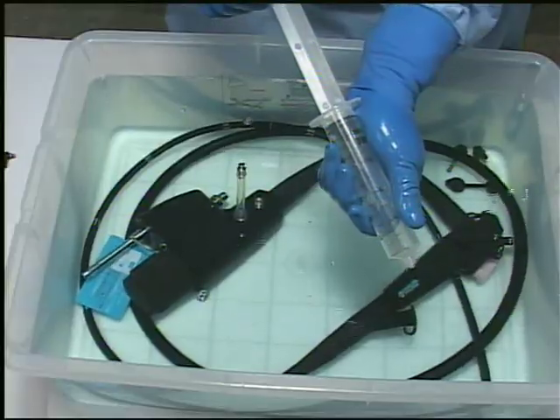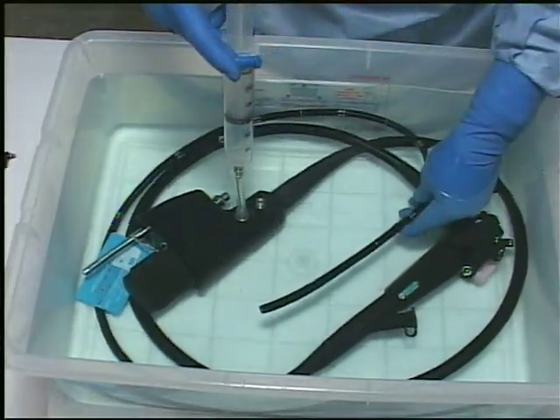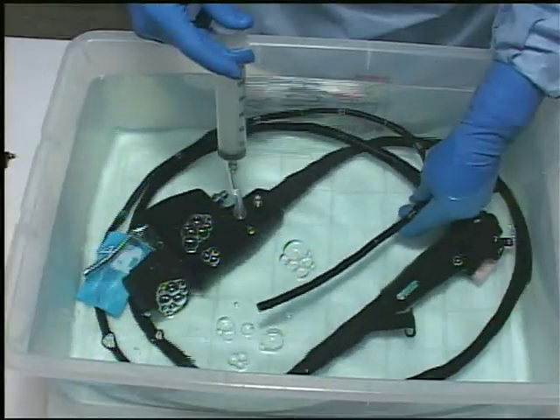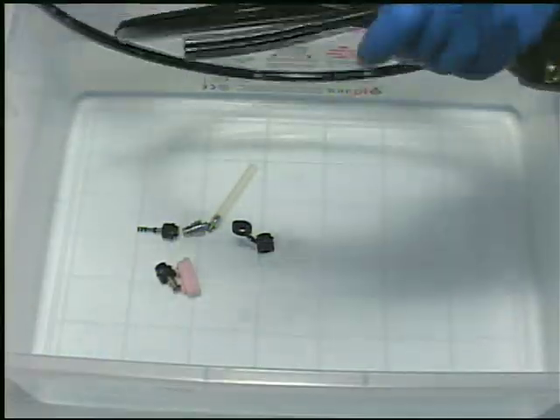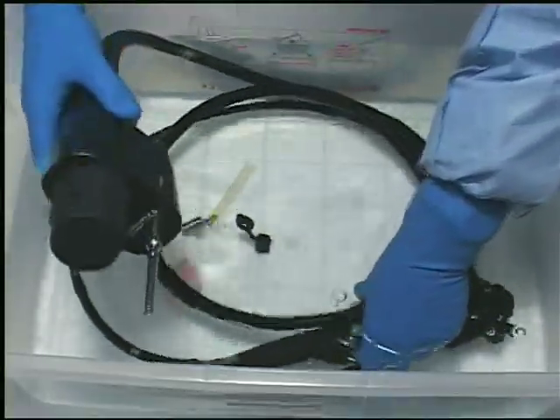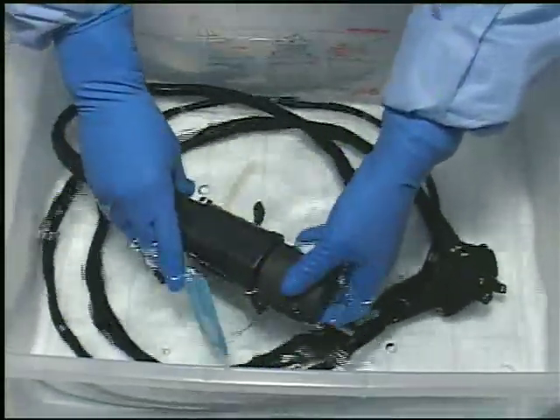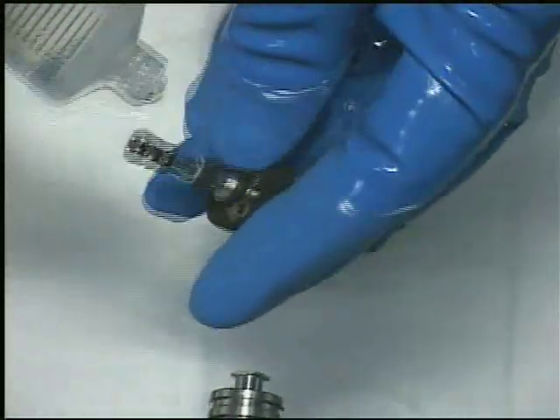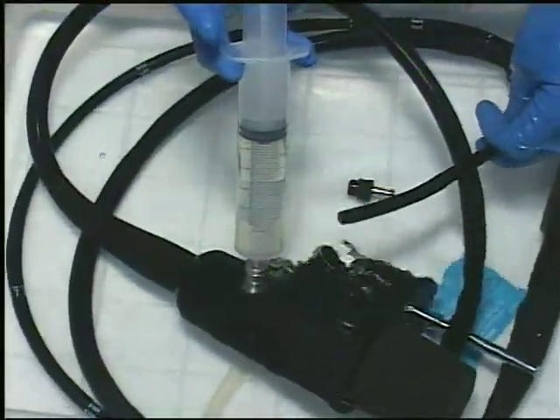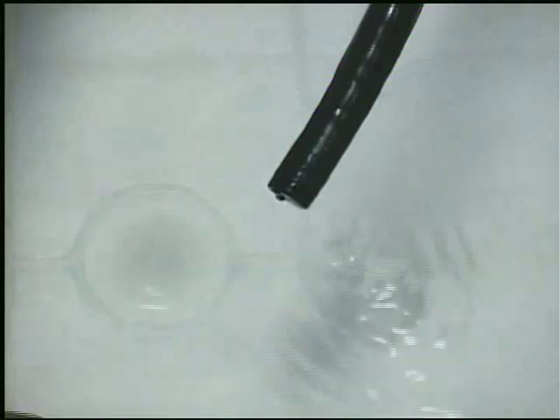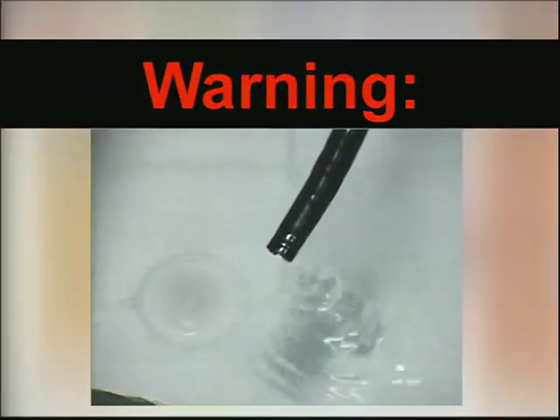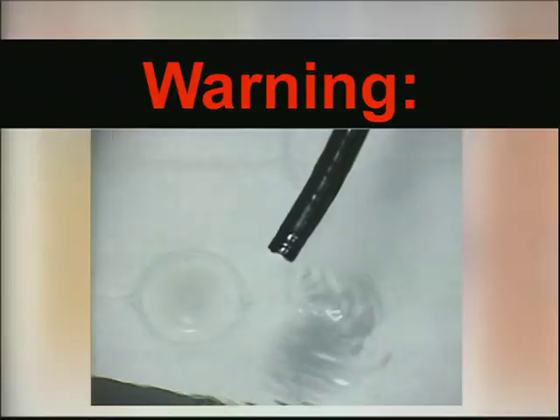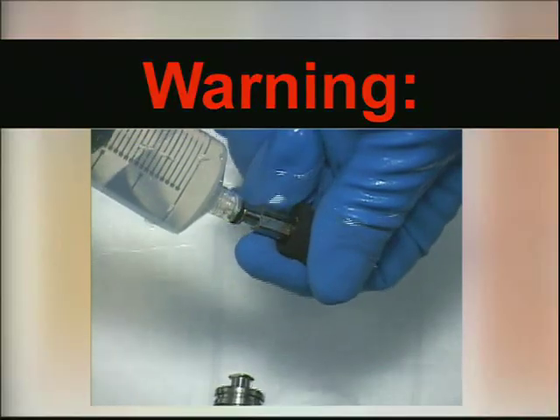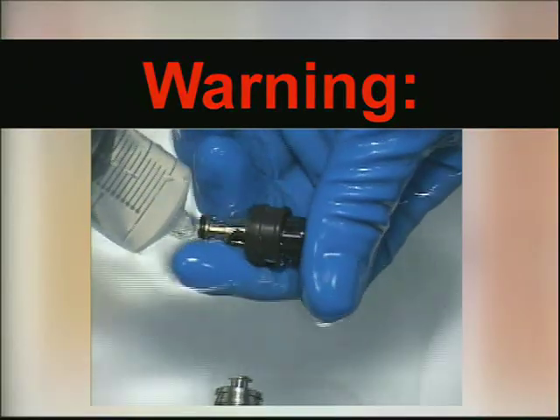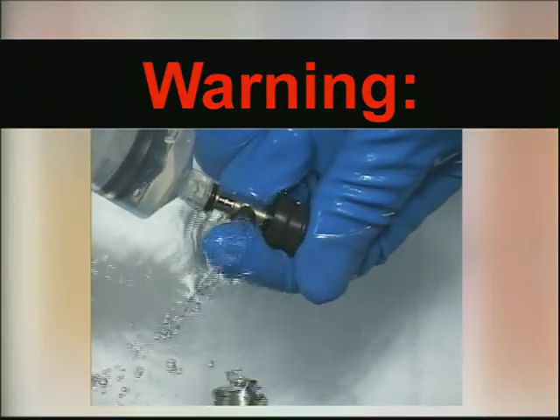Prior to rinsing, purge all internal channels with air using a syringe to expel residual detergent solution from the channels. Using clean water, immerse the entire endoscope as well as all removed components in a basin of clean water. Thoroughly rinse all items. With all cleaning adapters attached to the scope, flush all previously air-purged channels with clean water. Repeat. Warning: it is important that all internal channels, air, water, and suction instrument, external scope surfaces, and components be thoroughly rinsed with clean water to remove residual detergent solution.